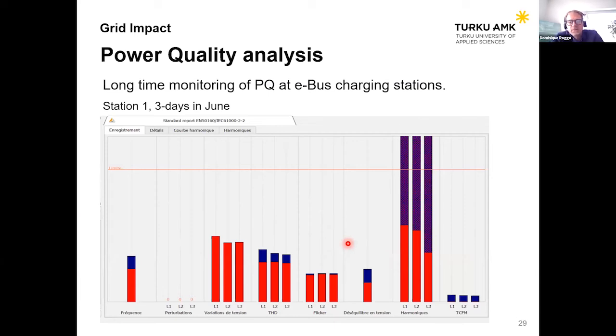In the bus charging station, everything looks pretty good. Here's a summary of those measurements, and you can see the limit is never really reached, if we consider the red line as 90% of the time, which is the requirement according to the rules. But we can see harmonics, oscillations on the grid that occur part of the time, maybe 5%, going over the limits.